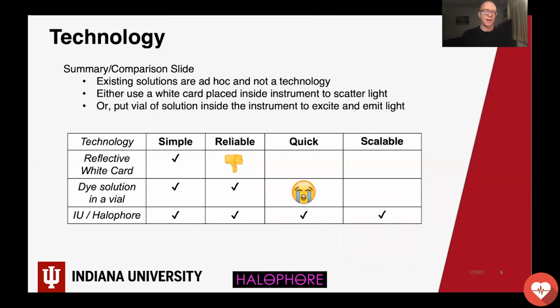Okay, the comparison slide is a little quirky because at the end of the day, there is no other technology standard out there. What we did hear about is reflective white cards that just reflect back the LED. They are simple, not too reliable because you are not matching the fluorescence signal, which is in a different area of the spectrum. So you could prepare a dye solution, place it into a glass vial. It is simple, it is reliable to a degree, but it became, upon discussions with a couple of our customers, a pain point. Whereas when you can reduce this to a polymer fluorescence standard, it's simple, it's reliable, and it's quick. And as a consequence of all that, it's scalable. You can put it in any instrument, in any place, under any condition.